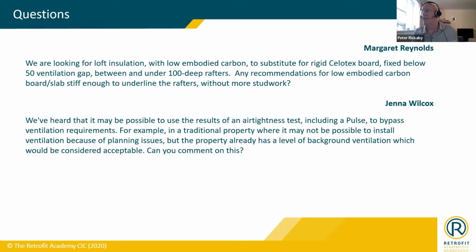Yeah, if we could just add to that a little bit. There is a scheme put together by the IAA that I've been told, though I don't know, has been accepted by TrustMark, or at least discussed with TrustMark, but which is about really applying the methodology that's in the new Part F of the building regulations instead of what it says in Annex C. And actually, I don't think that's compliant. The building regulations are minimum standards. Annex C is a best practice standard.